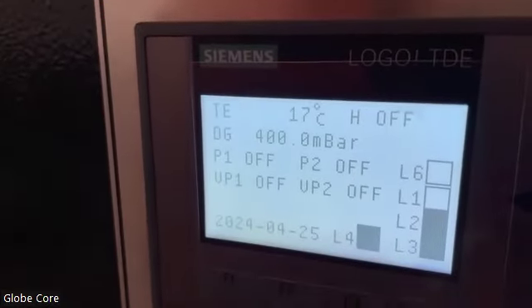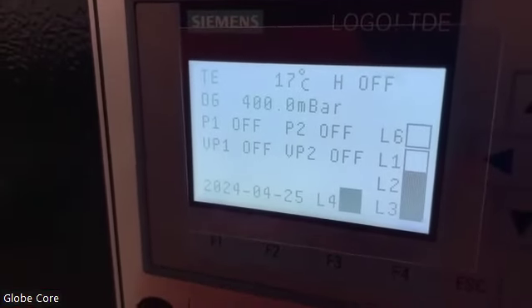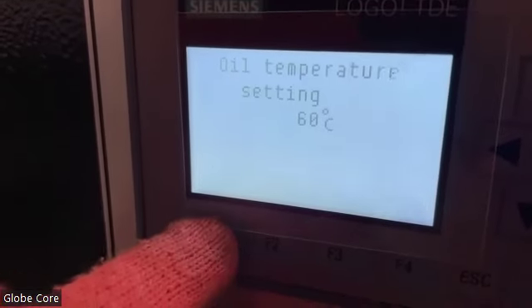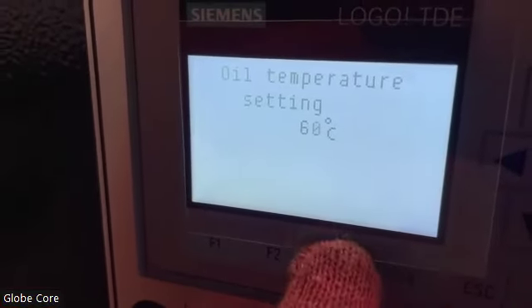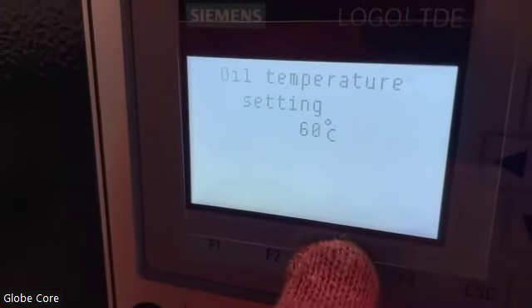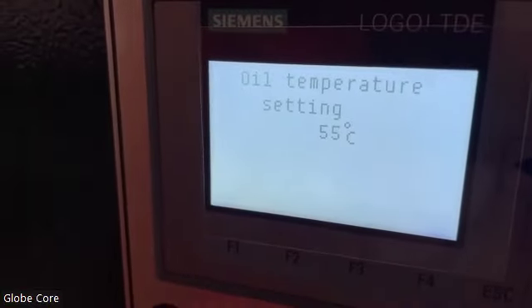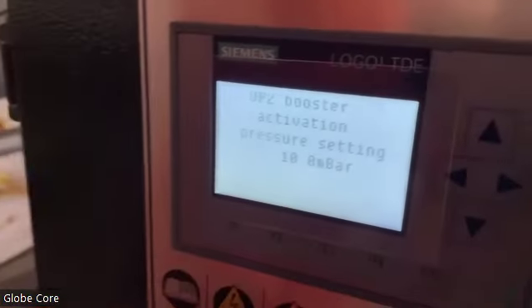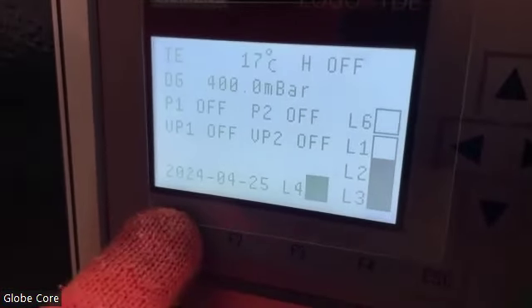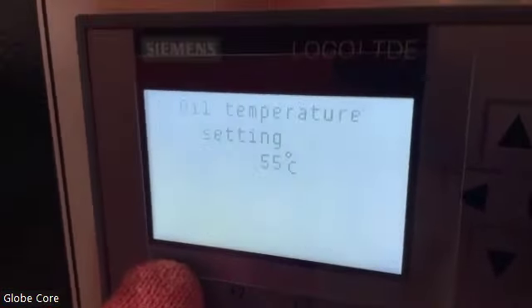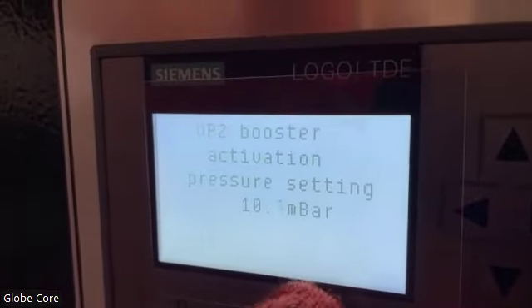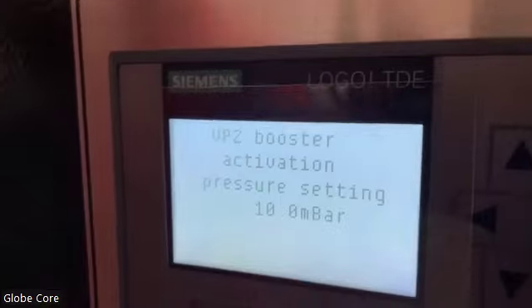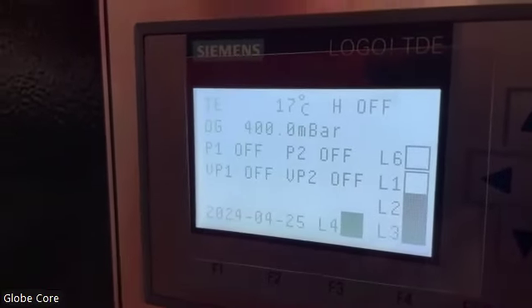So also by means of the controller, we can change the setting for operation temperature. To do this, we press the F1 button. Here we can see the oil temperature setting, and with the F3 and F4 buttons, we can raise or decrease the temperature setting. By pressing F1 once again, we go to the setting of the booster activation pressure. Now it's 10 millibar. Again, to change this value, we can raise or decrease it by the F3 and F4 buttons. Okay.